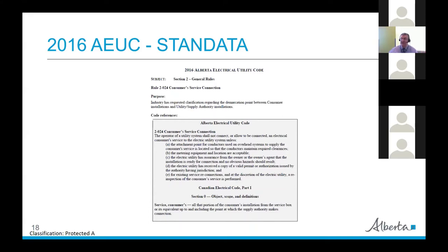In order to meet all the requirements, you need to know where the demarcation point or points are, so everybody knows which code regulates which portion. It can't be regulated by both — each portion of an electrical installation is either regulated by Part 1 or the utility code. If you have any questions about where that demarcation point is, the first person to ask is the Safety Codes Officers on both sides of it.